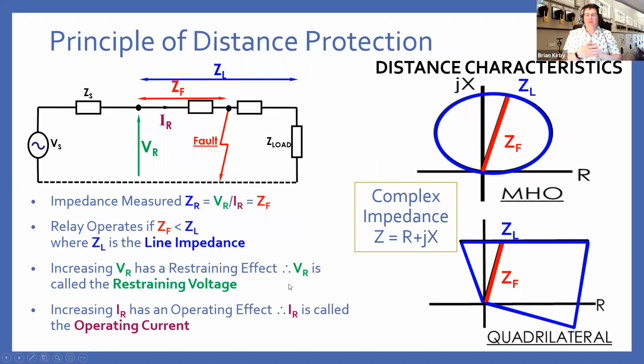Distance protection, what you're doing, we have a source and a source impedance. And at the point that we measure, what we're measuring is the voltage that is generated across our line and our load. And we calculate the impedance at that point by dividing the voltage measured by the current, and that gives us our measured impedance. Now, under normal conditions, ZR is greater than ZL, which is the impedance of your line, and you would say the system is healthy.